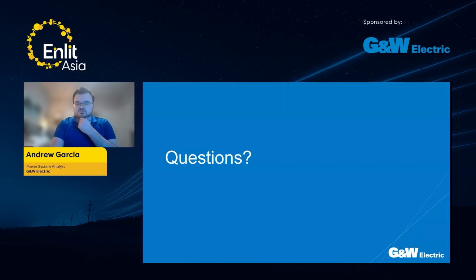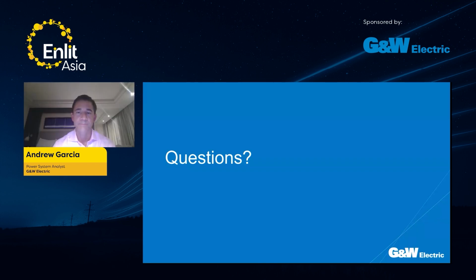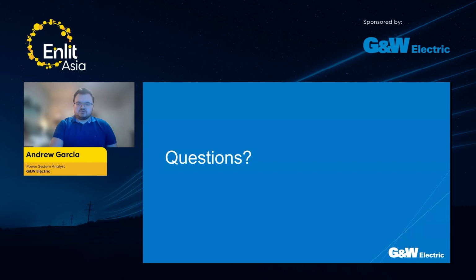Yes. What is the effect of voltage surge or lightning strike to a current limiting device in terms of its operation or functionality? That entirely depends. I'm not certain exactly how the lightning strike would affect a solid state breaker, for example. It's an electronic device. I assume that they do have some method, that I'm not too familiar with, to limit the effect that a lightning strike or voltage surge could cause on that system. However, in a lot of the other devices, current limiting protectors and the traditional devices like reactors and fuses, lightning strike would probably have a minimal effect on your system, provided that the lightning strike or voltage surge does not exceed the level that your system is rated for in terms of impulse voltage. Right. In which case you could have a flashover, but that's going to happen with a current limiting device or any other device in your system.